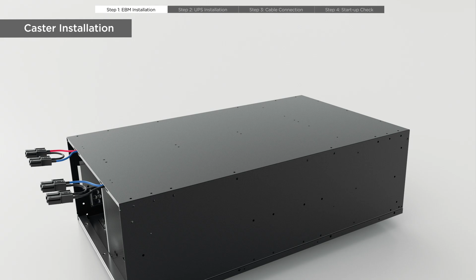Turn the EBM over and install the casters with 4 silver hex head screws per caster. Flip the EBM back to its upright position and activate each caster brake after positioning. Attach the 4 stands using 2 black pan head screws and 1 silver hex head screw per stand. After finalizing the position, depending on the requirement, users may choose to secure the stands to the floor with 1 expansion bolt per stand.